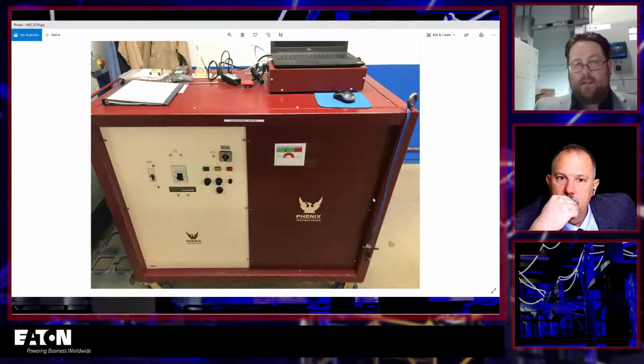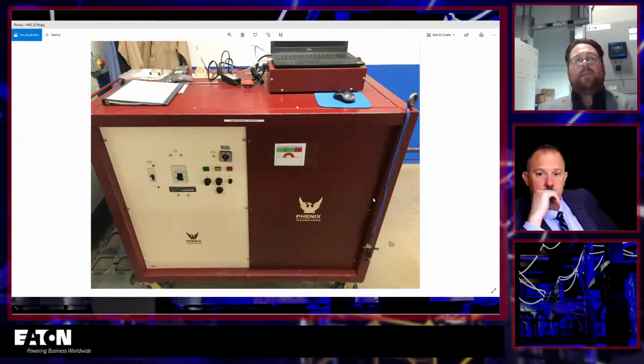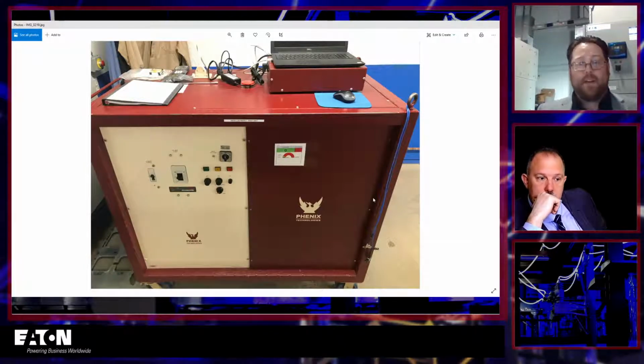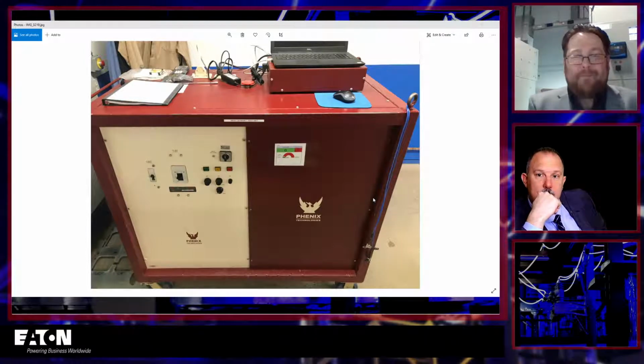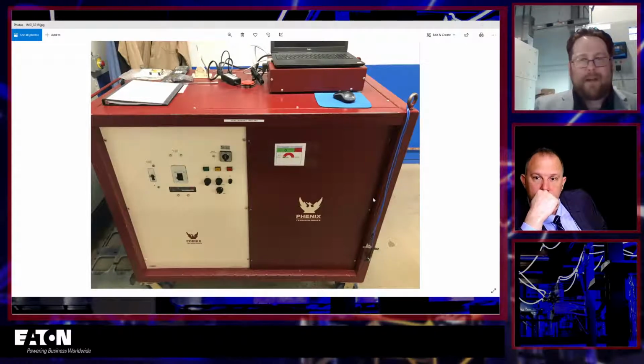Yeah, and really, if you go back through history, and let's talk just breaker testing in general terms here. When we had our series trip devices decades ago, every device was primary injection tested. That was your only option to test it. Then, as you showed on your timeline, around 1970-ish, microprocessor-based devices were coming in.